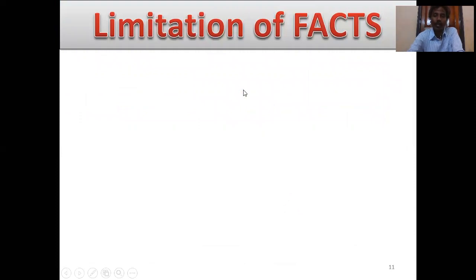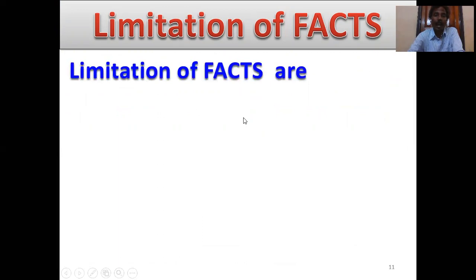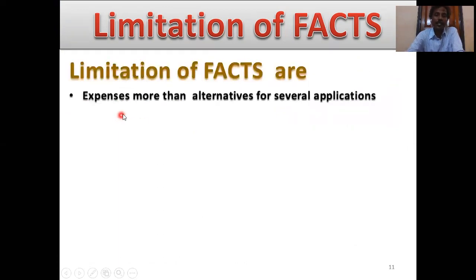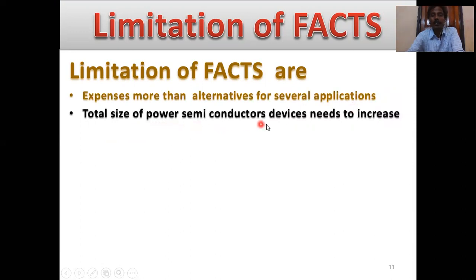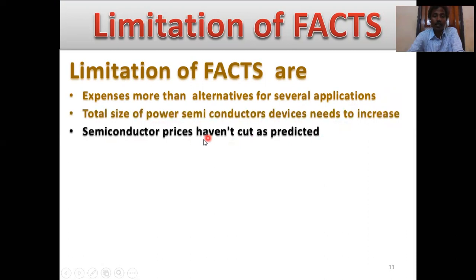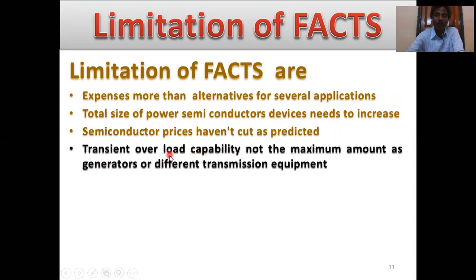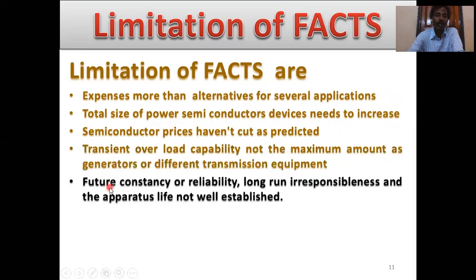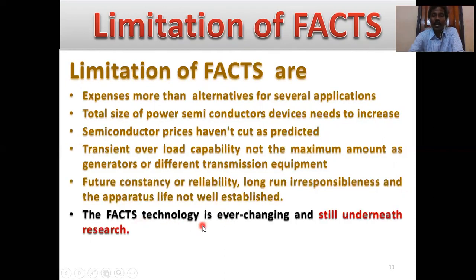Limitations of FACTS, this is the important section. What are the limitations? It is more expensive than alternatives for several applications. The total size of power semiconductor devices needs to increase. Semiconductor prices have not come down as predicted. Transient overload capability is not as high as that of generators or other transmission equipment. Future reliability and long run dependability, and the equipment life, are not well established. FACTS technology is ever changing and still under research.